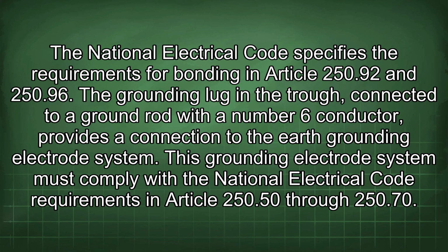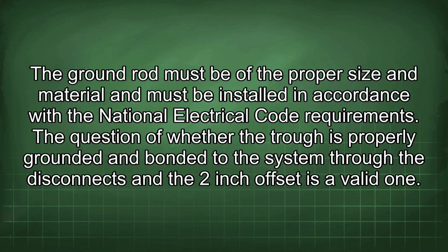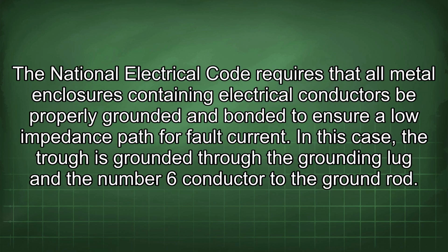provides a connection to the earth grounding electrode system. This grounding electrode system must comply with the National Electrical Code requirements in Article 250.50 through 250.70. The ground rod must be of the proper size and material and must be installed in accordance with the National Electrical Code requirements. The question of whether the trough is properly grounded and bonded to the system through the disconnects and the 2-inch offset is a valid one. The National Electrical Code requires that all metal enclosures containing electrical conductors be properly grounded and bonded to ensure a low impedance path for fault current. In this case, the trough is grounded through the grounding lug and the number 6 conductor to the ground rod.